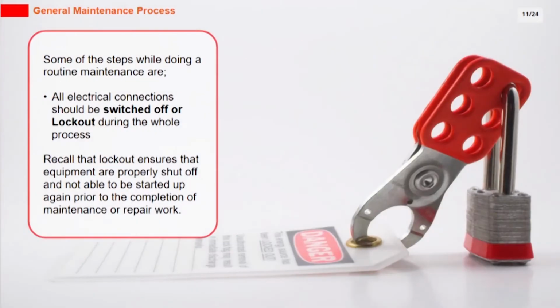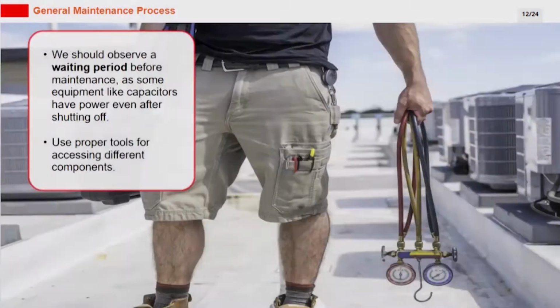Some of the steps while doing a routine maintenance are: all electrical connections should be switched off or locked out during the whole process. Recall that lockout ensures that equipment is properly shut off and not able to be started up again prior to the completion of maintenance or repair work. We should observe a waiting period before maintenance, as some equipment like capacitors have power even after shutting off. Use proper tools for accessing different components.